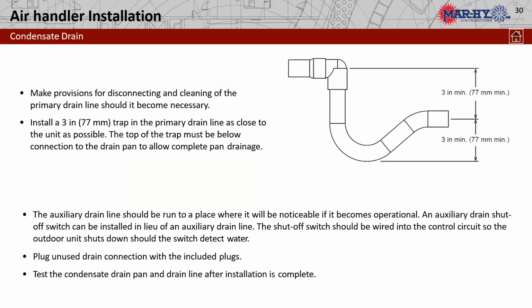Now again, when you are running ECM motors, you need to run deeper traps. We need to be at least 3 inches on our trap depths. That way we're not sucking air back into the drain pan and having a major water problem. You will sometimes see that if you're doing short traps on ECM motors, they can pull a lot of air and pull that water right out of the trap, up into the drain pan. Then we wouldn't be draining, and we would have issues.